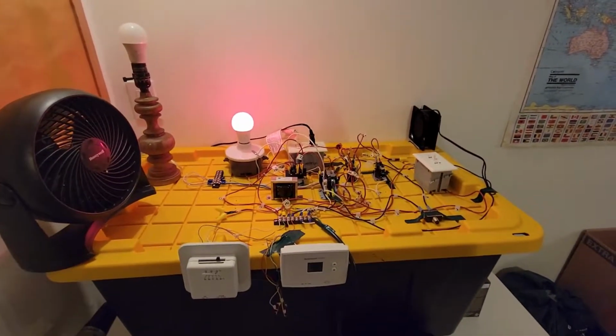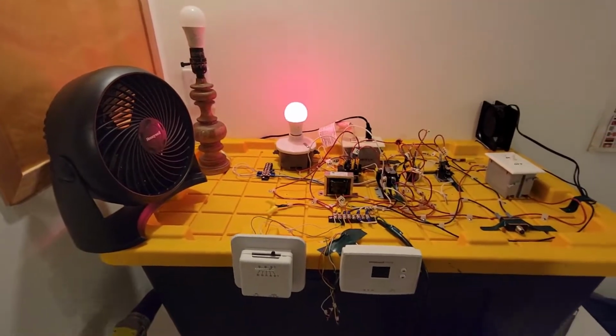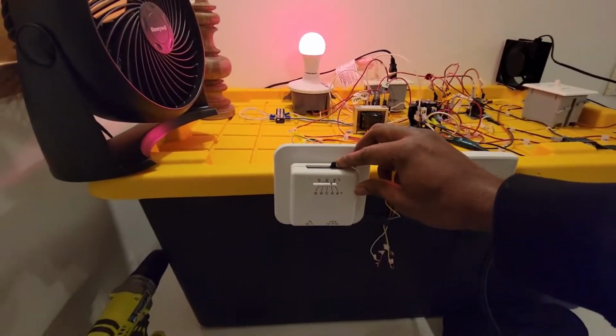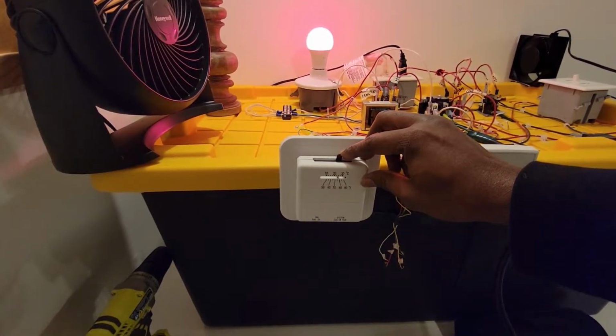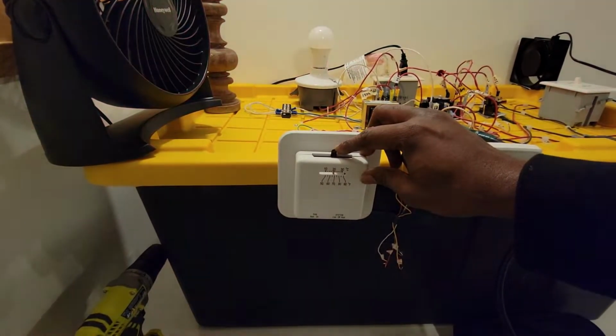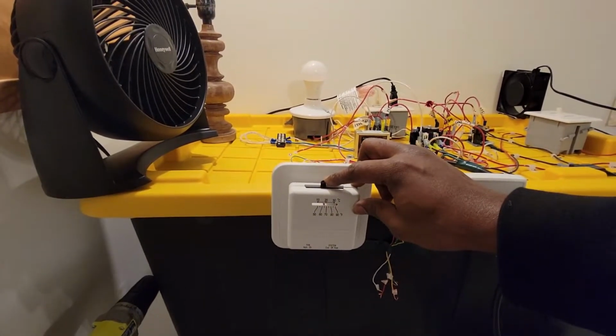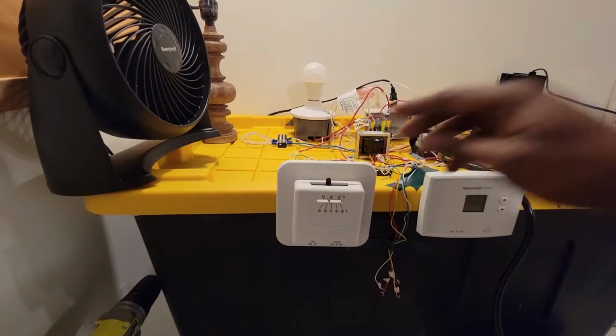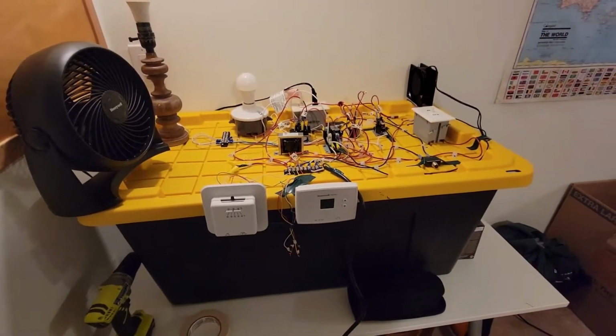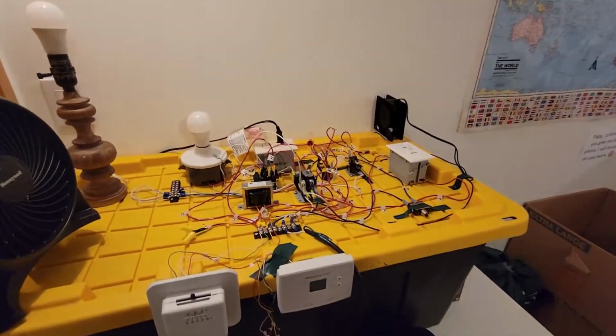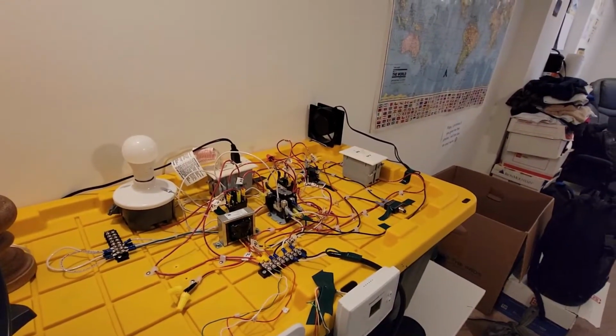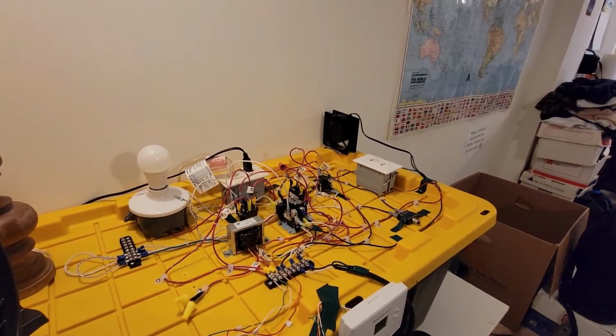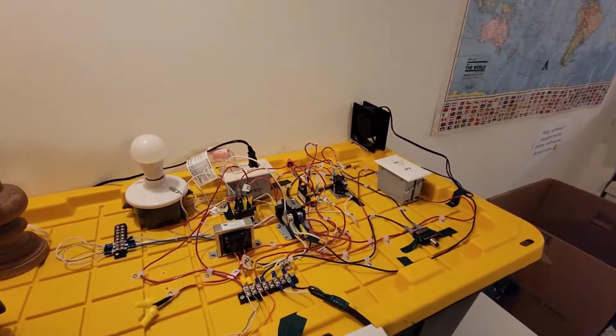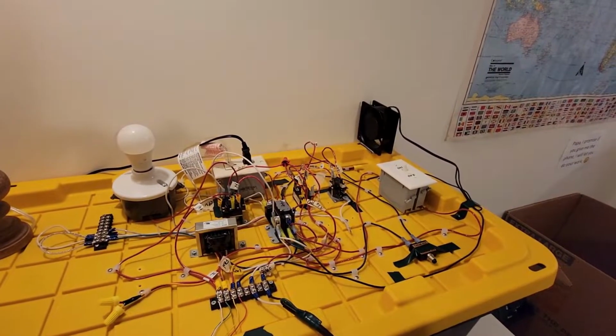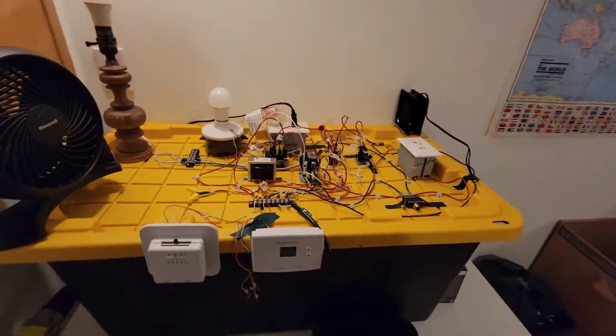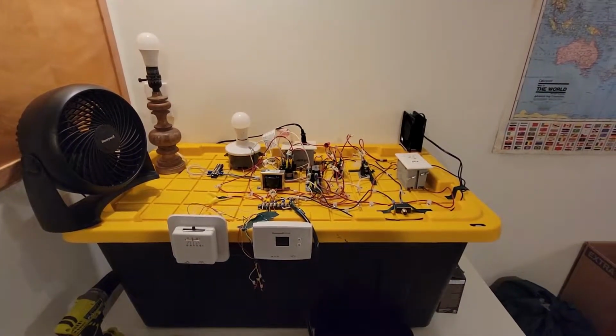Let's say it reached the desired temperature. Our bimetal coil senses that and disconnects, and that turns off my heat. But the blower fan is still going because I still have a bit of heat in the heat exchanger, and then that's going to turn off when the heat sequencer drops down. All right, it drops down by cooling off.